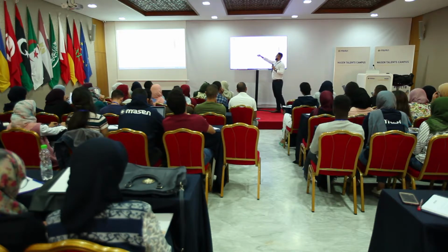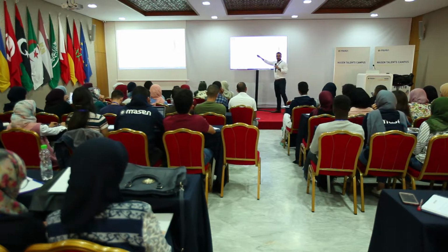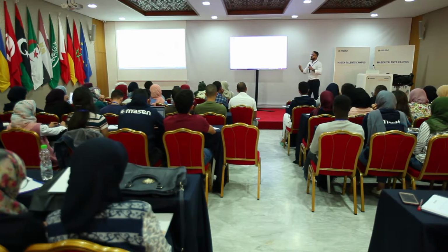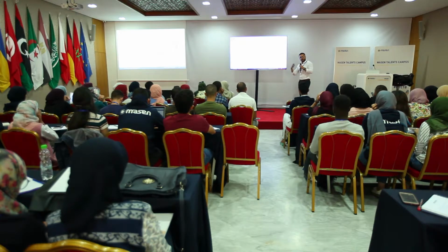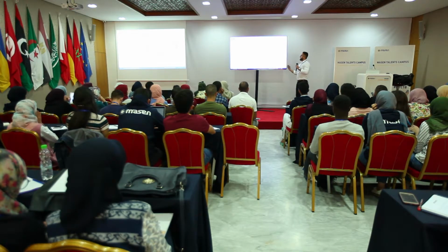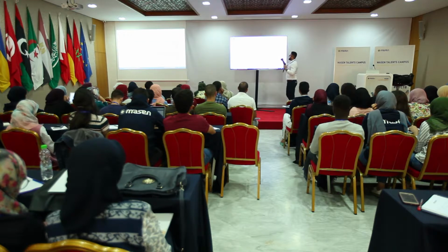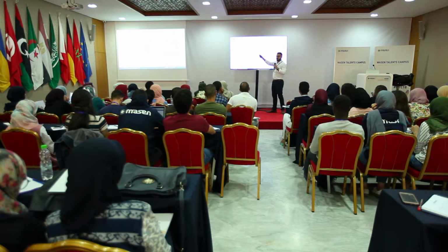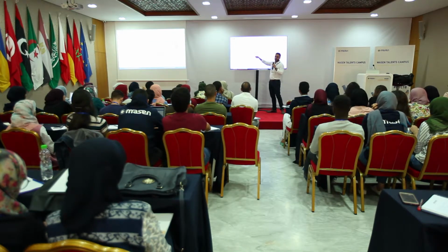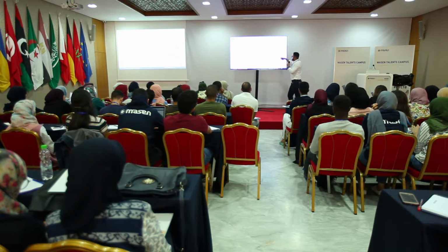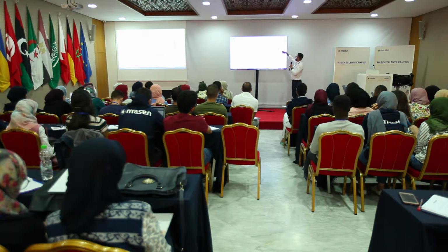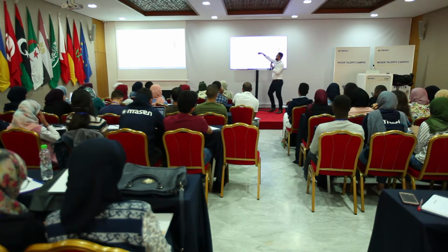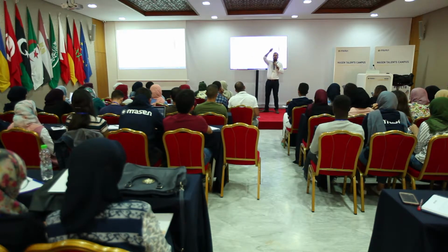So that's the reason, the whole logic behind how to size both the solar field, the storage, and the power block. Those are the things that you're mainly sizing. And again, you could have, let's say, whatever collector field, a solar tower, with a large storage unit and a relatively small turbine, 120 megawatt, and then operate for 24 hours. Like the one I said in Chile. The one in Chile has 110 megawatt with 18 hours storage. That plant will operate something like this all the time, ideally, right?